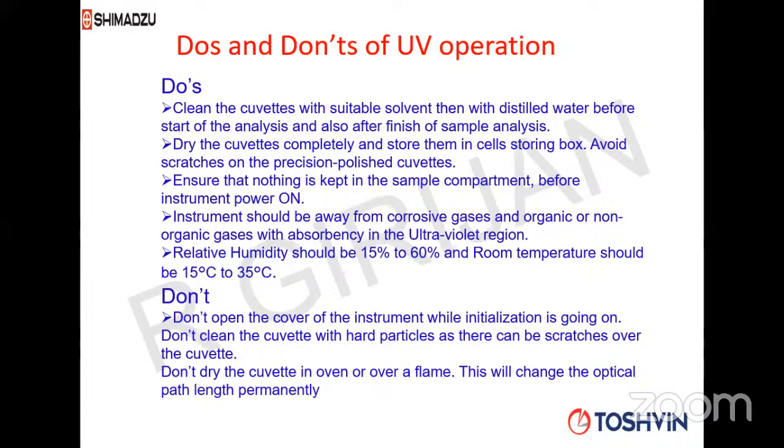And when you are starting the instrument, during this auto check, you should never open the instrument cover. That's called the initialization step. So when you are starting the instrument in the morning, see that nothing is there inside the sample compartment. If something is there, please remove that. And then you go for an auto check. Okay, so these are the things which people have to follow.